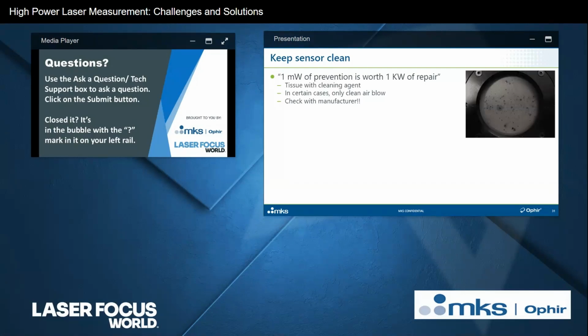Here you see a thermal sensor with what most likely started off as some kind of organic debris that splashed onto the sensor. Now, it would have been very easy to clean that off with a soft tissue and a cleaning agent, ethanol, acetone, something like that, but it wasn't cleaned off, and the next exposure to laser power burned that stuff on. There's no way to clean that off anymore. That sensor needs a relatively expensive disc replacement, and that's unfortunate. So again, one should try to keep the sensor clean rather than figure out what to do about the fact that it wasn't kept clean.